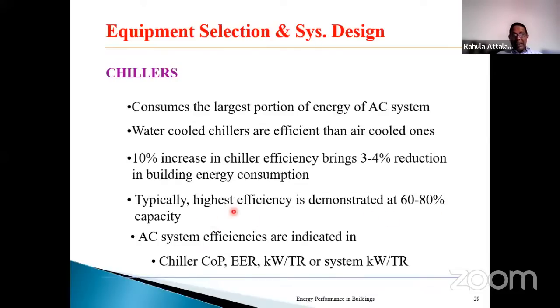This I have discussed. Any mechanical equipment will have a part load efficiency much better than the full load. The efficiency values are indicated by coefficient of performance. These are the typical indicators. Energy efficiency ratio, or EER, or another indicator is kilowatt per ton of refrigeration. So this is for the chiller. For the entire system, we can also have kilowatt per ton of refrigeration. This kilowatt would be all the electricity, the power consumption inclusive of the chiller, pump circulation power for the chilled water, condenser water, and fans, etc. These are the typical indicators normally used.